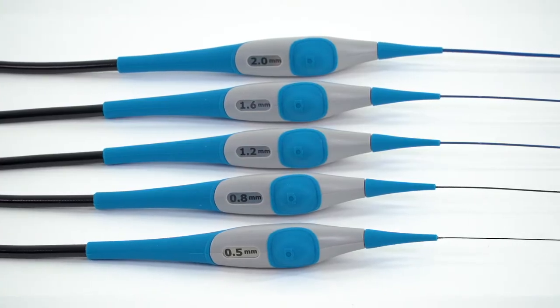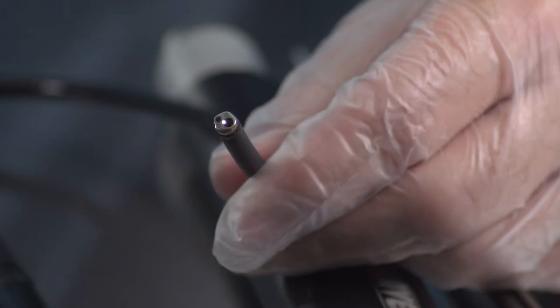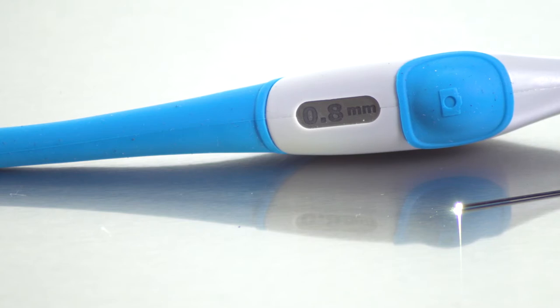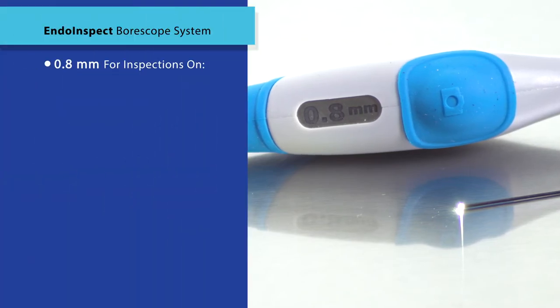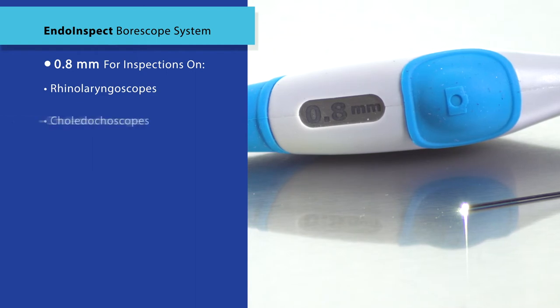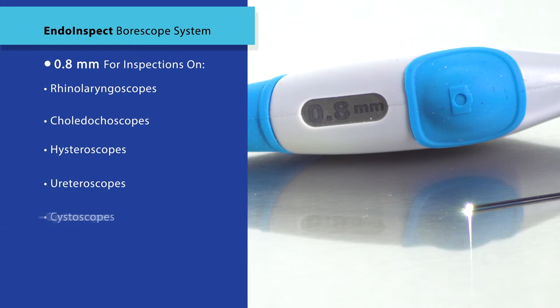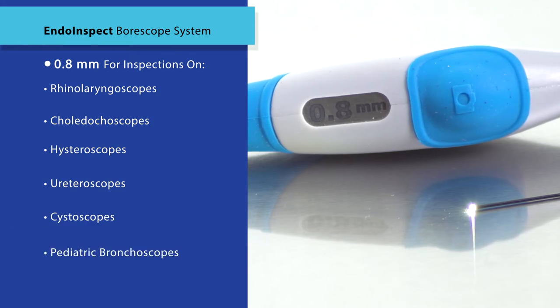Five different diameter Borescopes are available. The smallest has a diameter of half a millimeter and is perfect for inspection of super small channels. A 0.8 millimeter fiberscope is suited for inspection of smaller lumens found on rhinolaryngoscopes, choledochoscopes, hysteroscopes, ureteroscopes, cystoscopes, and pediatric bronchoscopes.